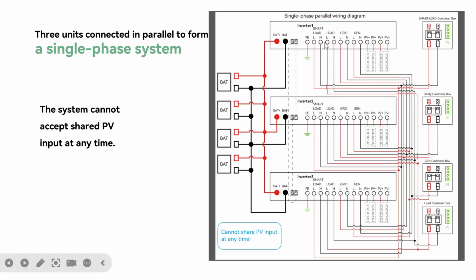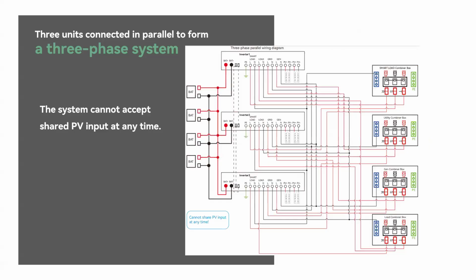As for the exact cable wiring, I think it depends on the actual installation on site. And there is a diagram for the three-phase system. As you can see here, we can also share the batteries between inverters but cannot share the PV input. Each inverter must have its own separate PV input. As for the three different phases, each inverter represents one phase. For example, inverter one is phase R, inverter two is phase S, and inverter three is phase T. As you can see from the diagram, R, S, T here.